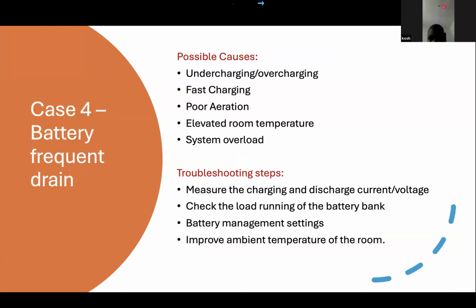So then case number 4, battery frequent drain. Possible causes: undercharging, overcharging, fast charging. That can cause sulfation as well. Poor aeration, elevated room temperature, system overload. The troubleshooting steps: you have to measure what your charging currents are to the battery, and what your discharge current and voltage are also. Then check the load running on the battery bank. Are you fast charging or are you fast discharging?